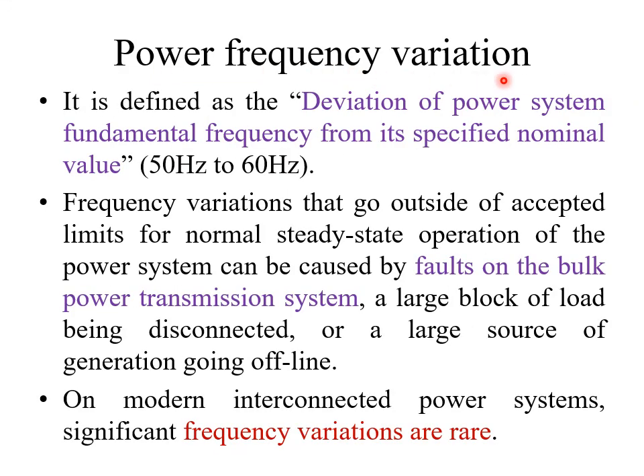Power frequency variation refers to any variation in the system frequency. For example, in a 50 Hz system with a tolerance of ±2 Hz, anything above 52 Hz or below 48 Hz is considered a power frequency variation. If the variation is large, it affects the entire transmission and distribution system with severe consequences. With modern technologies, such frequency variations are very rare. That concludes the discussion on power quality issues. Thank you.